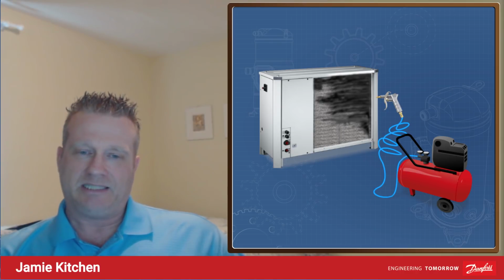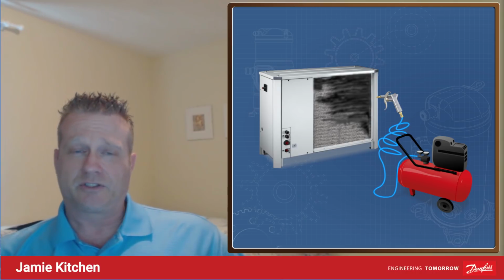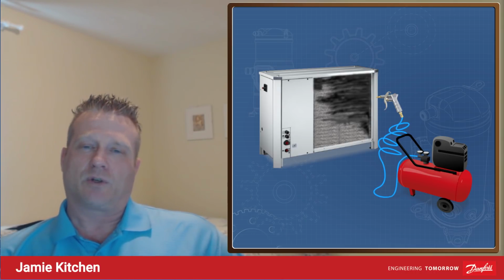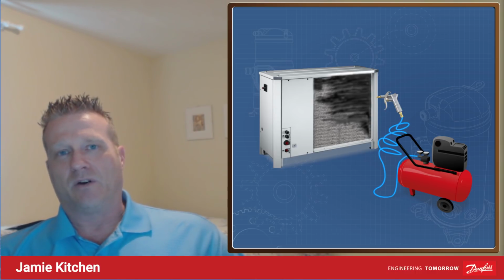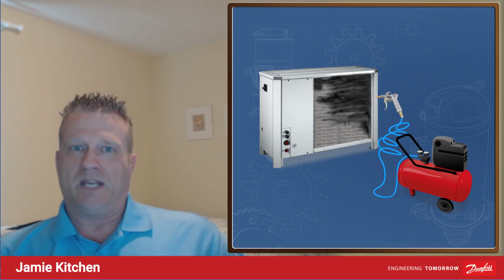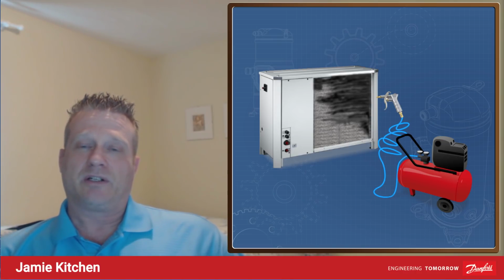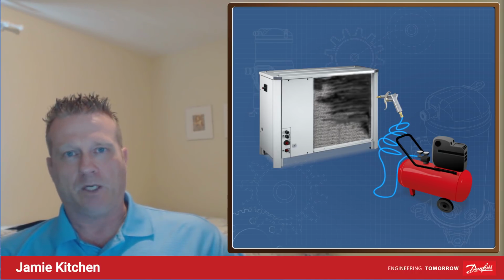And I'm talking about easy cases. A lot of times, air being recirculated in a condenser is a real issue. Condensers are stupid. They don't know what the actual outdoor ambient temperature is. All they know is the temperature of the air that's entering into them. So they don't care if it's 85 degrees outside. If it's recirculating the air and the air going in is at 100 degrees, they think it's 100-degree ambient outside, and that's the way they're going to operate. Okay, so again, keep in mind that this is an issue that needs to be addressed, even though we're just talking about compressors. We're talking about startup commissioning or preventative maintenance. Okay, that should all be on your list when you're out there.